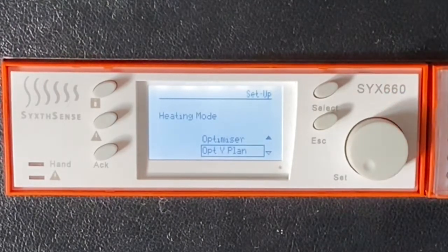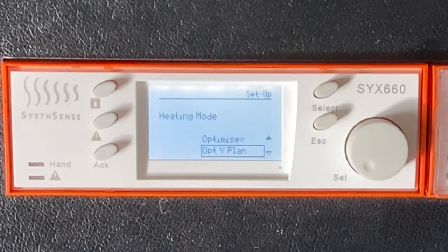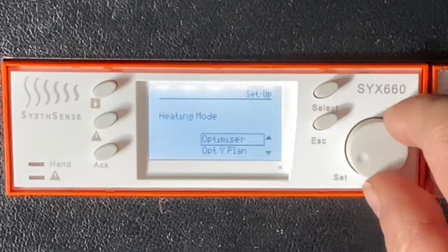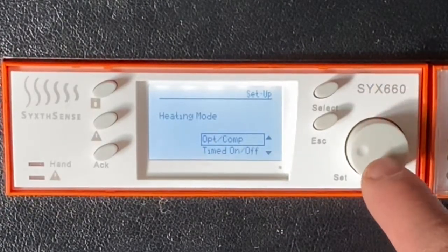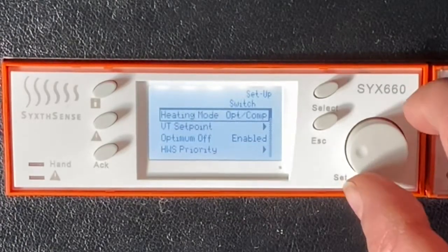And then finally there's an optimized Y-plan application for large domestic applications, where you have the traditional Y-plan arrangement for the heating system with the motorized valves and hot water arrangement, both sharing the boiler, but there is the option there of optimizing it if that's required. So anyway, we're going to choose optimizer compensator for our application.